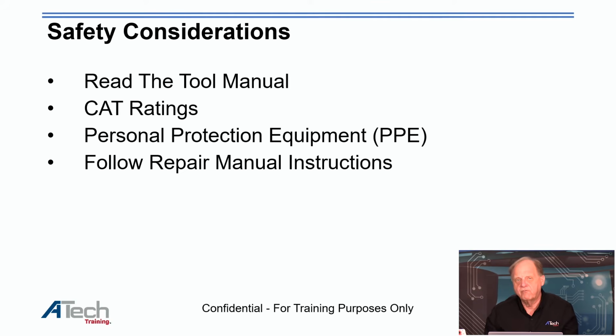The other thing is you have to start off with personal protection equipment, PPE. You'll hear that a lot if you're going through some of the tests, L3s and others for hybrid work. So some people will wear cotton gloves, then rubber gloves, and a leather glove on top of that for protection. You're testing this circuit, you want all the protection you can to make sure you don't get shocked, or your heart might even stop if you hit it at the wrong point. Another thing most people don't think about is having protection around you to make sure nobody just comes up to you while you're working on it.